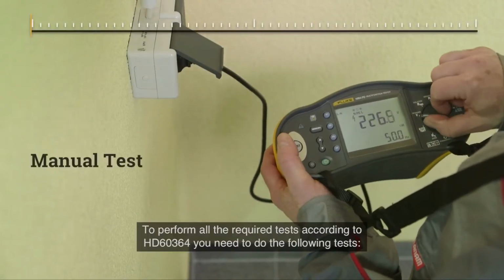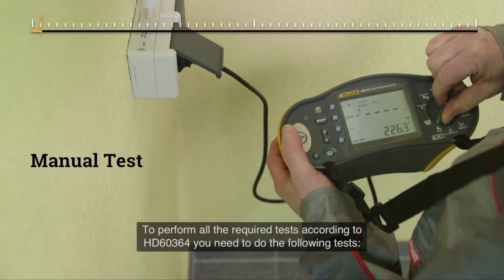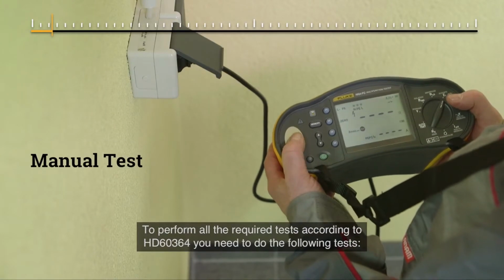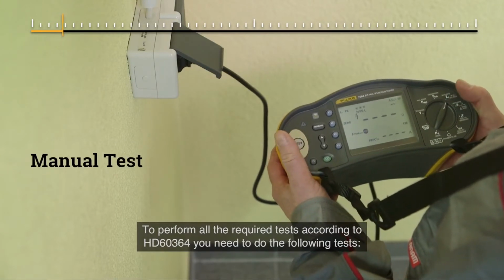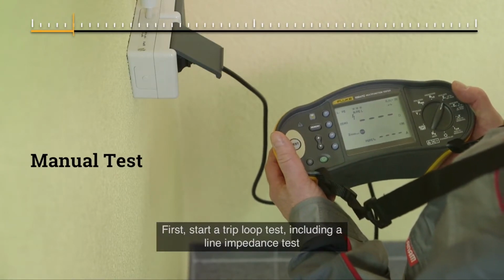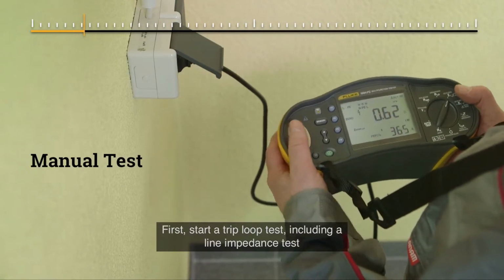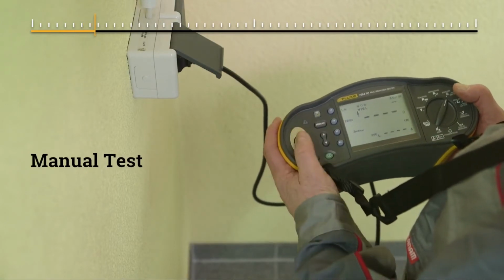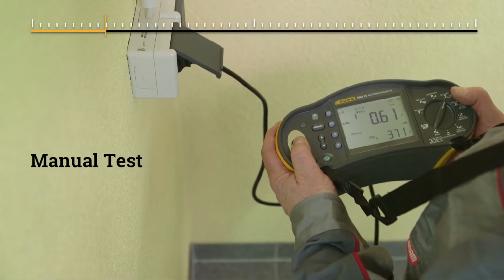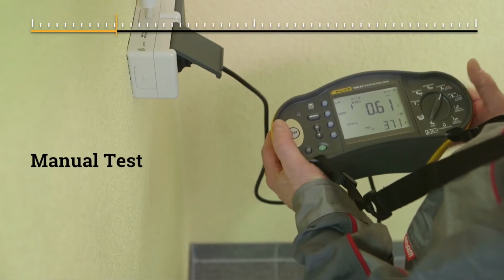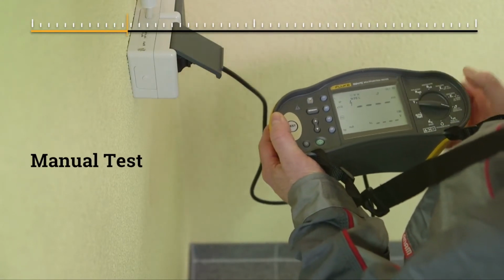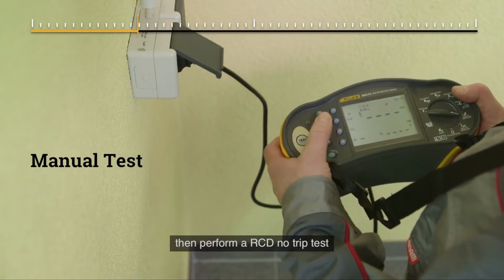To perform all the required tests according to the HD 60364, you need to do the following tests. First, start a trip loop test, including a line impedance test. Then perform an RCD no-trip test.